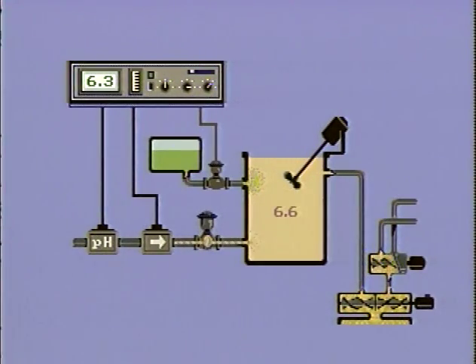What had happened in the plant was that the controller worked well to add the correct amount of acid based on the pH of the raw material and the flow rate. But the raw material was still more alkaline than the specifications allowed, even after the acid was added. This was caused by the variations in concentration of the acid additive, which was a disturbance variable that was not measured in the feed-forward system. There was no signal to the feed-forward controller indicating that the pH of the mixture was still too high.